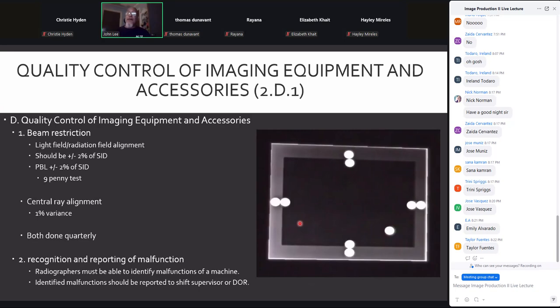The diameter of a penny radiographed sitting on the receptor at a 40-inch SID is exactly 2% of 40 inches SID. So we put those pairs of pennies in the middle of the long collimator areas, we turn the light on and put our pennies down. Then we'll make the exposure. The light field is represented by where the pennies connect.